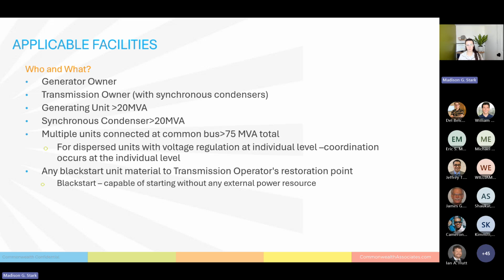And then the last unit that this really applies to is any black start unit. So what is a black start unit? That is a unit that can be turned on without any external power requirements. A lot of generators require some form of external power source to get the turbine spinning, to get power going, to get the generators excited. But a black start unit is one that's independent and can run independently. These are important because they're critical for restoring blackouts. So any black start unit, regardless of size, falls under PRC 19 coordination requirements.